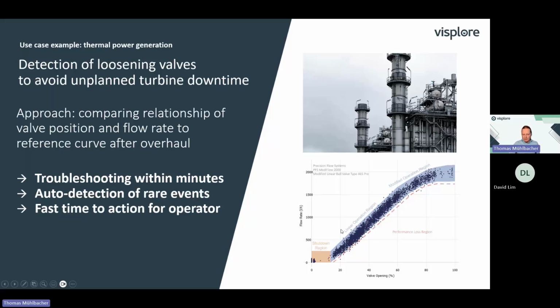If you take a look at this image in the bottom right, you'd see that for a certain recorded opening position of the valve, there's a certain corridor of expected flow rate - this is what you see in blue. This is usually also given or known for a valve from the vendors, for example.